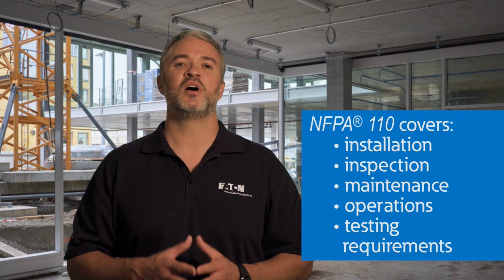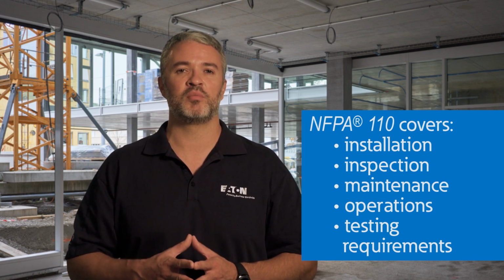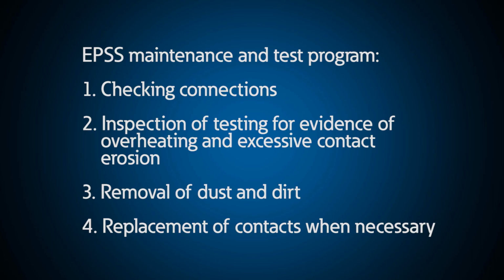NFPA 110 presents installation, inspection, maintenance, operation, and testing requirements as they pertain to the performance of the EPSS up to the load terminals of the transfer switch. It requires that transfer switches be subjected to a maintenance and test program that includes all of the following: checking connections, inspection or testing for evidence of overheating and excessive contact erosion, removal of dust and dirt, and replacement of contacts when necessary.